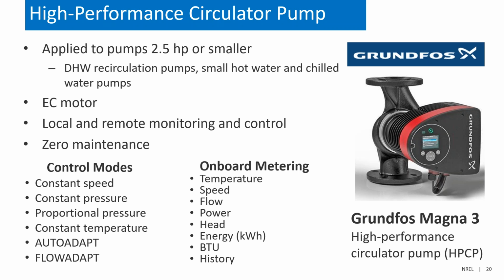These ones that we monitored also have a number of built-in control modes and onboard monitoring. Essentially it's like an integrated pump with integrated sequences of operation and integrated metering systems that are all within the pump. And so you can see we have a number of different control modes that can be operated within the pump.